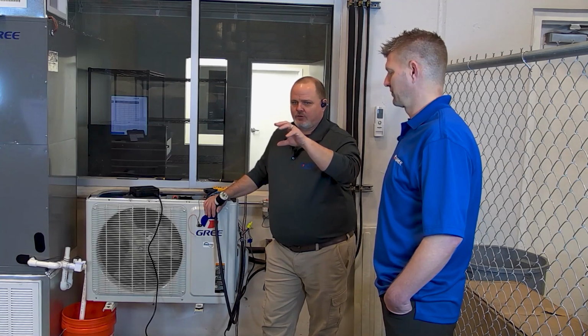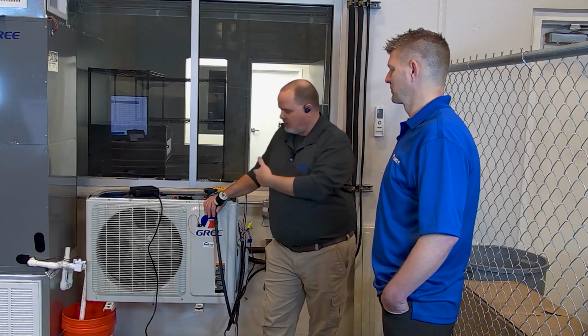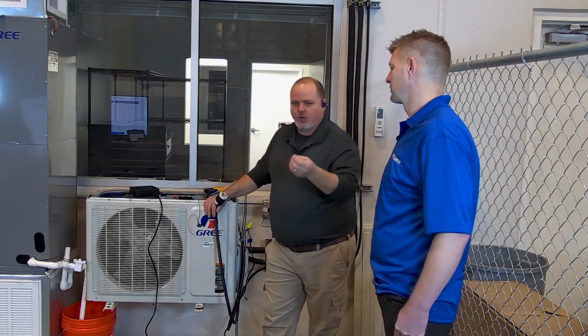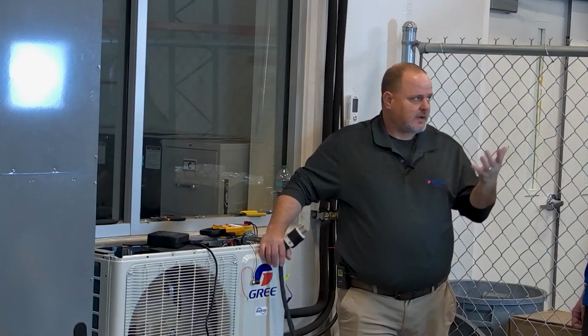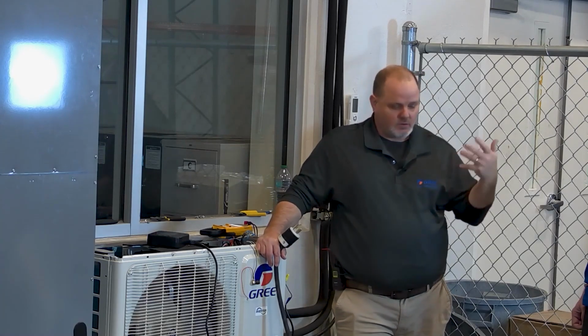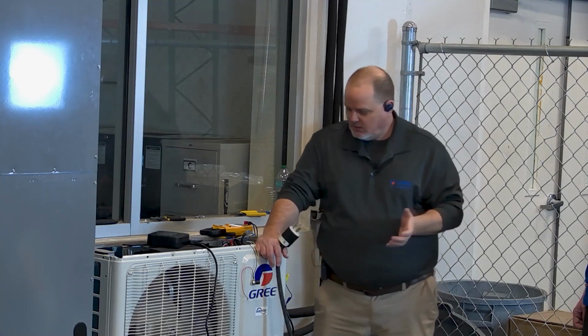You've got your 1, 2, 3 wires going to your indoor unit. All you do is double up on those, 1, 2, 3, and then you're able to just turn the machine on, turn the service tool on, and select data monitoring, and the machine will just run. That data monitor could be on there for years if you left it there. All it's doing is monitoring the operation of the unit. But we can also do the simulation. So let's do the simulation.